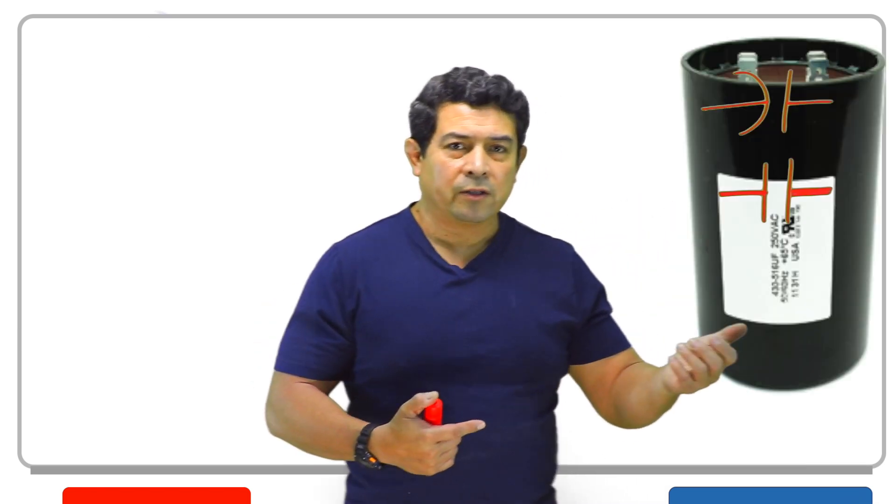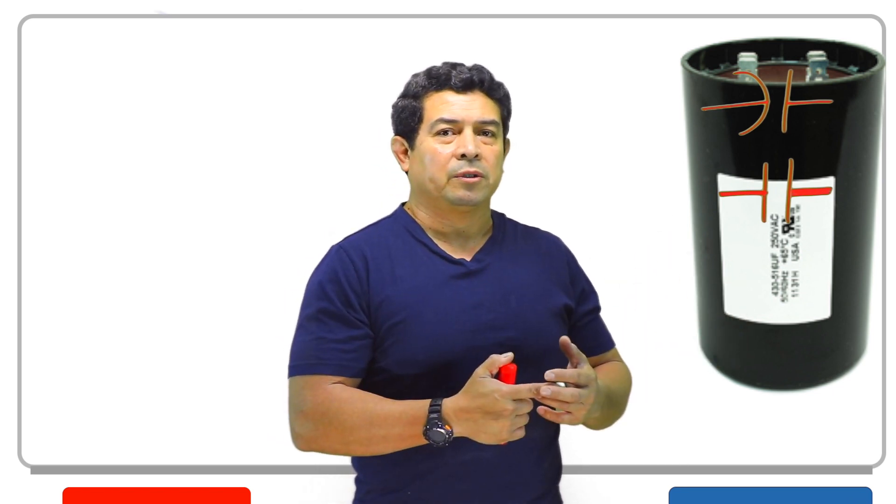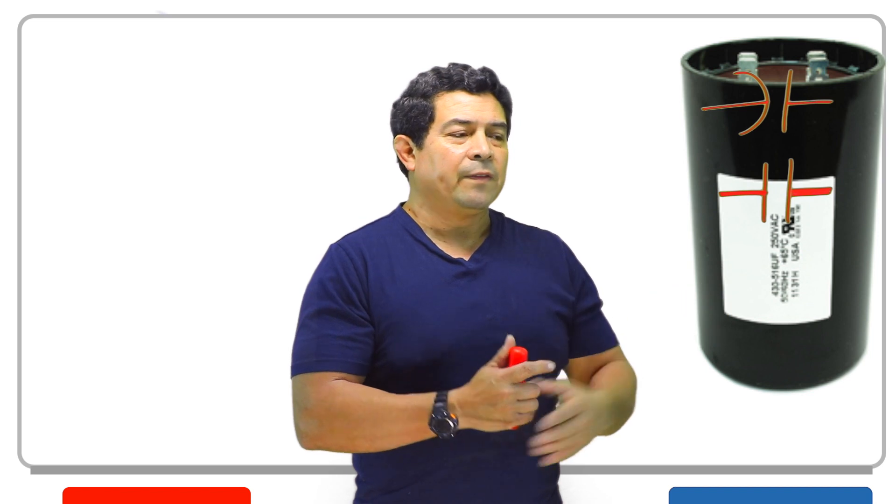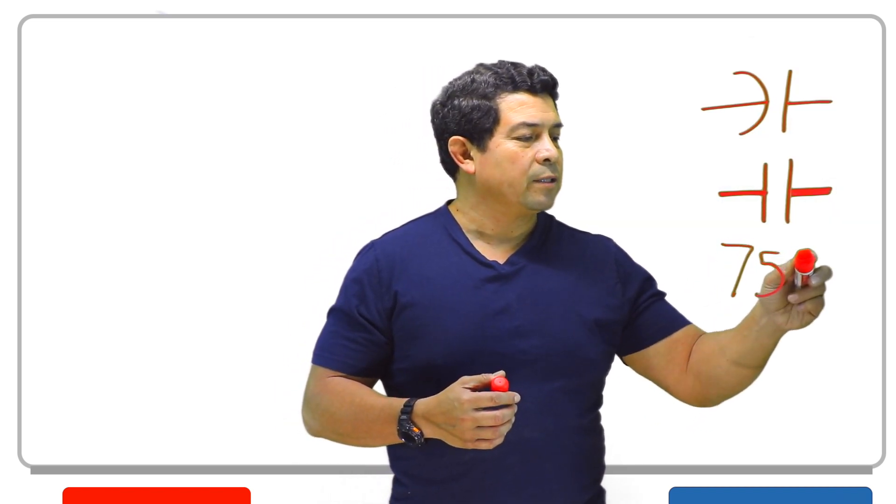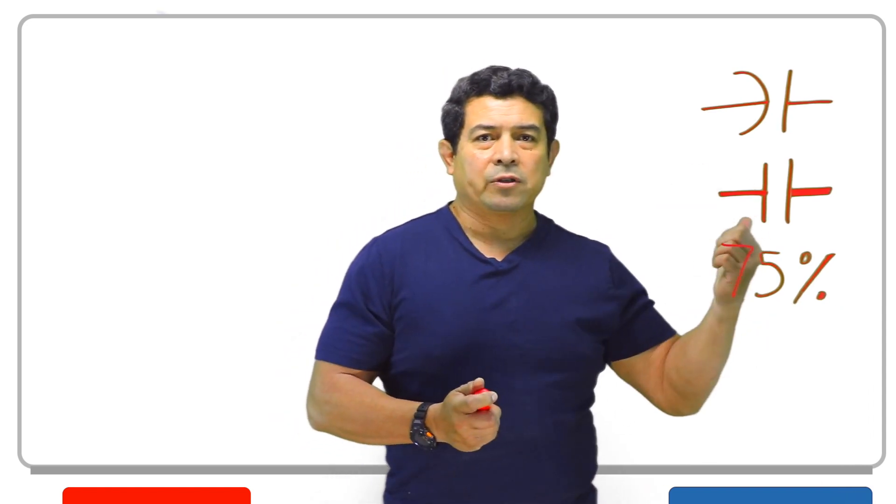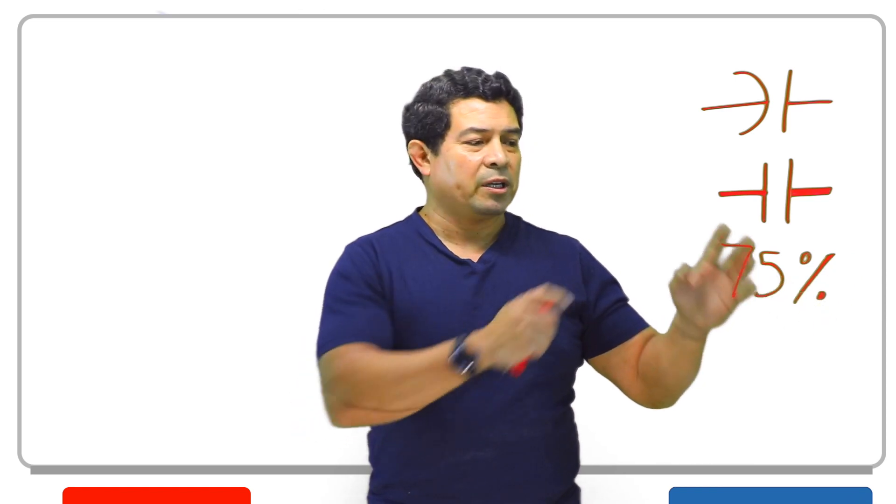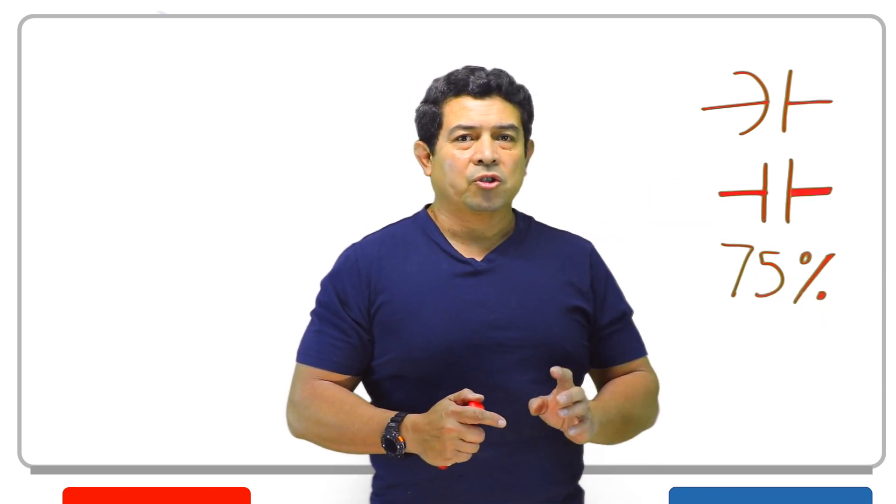On the other hand, the start capacitor is going to be only used when it starts up. And then, once it starts up, at about 75% of the motor speed, it's going to be taken out of the circuit. They're going to take the capacitor completely out because it is a start capacitor. It's only used on startup.